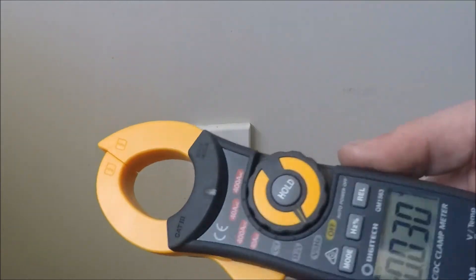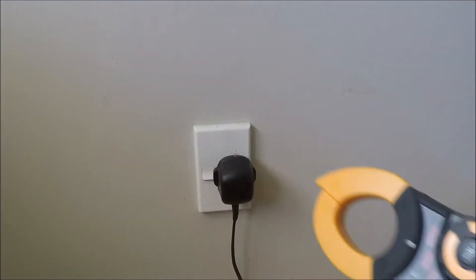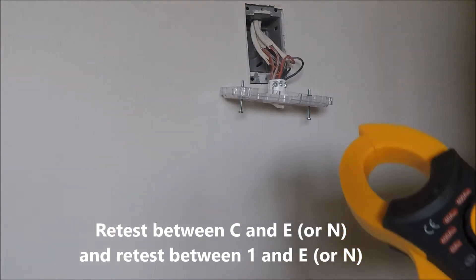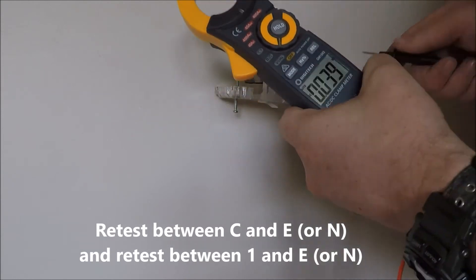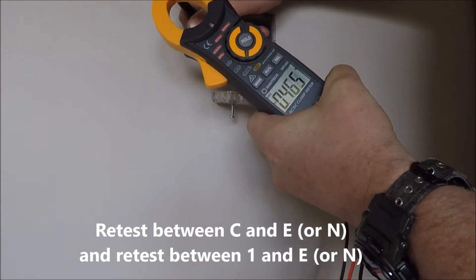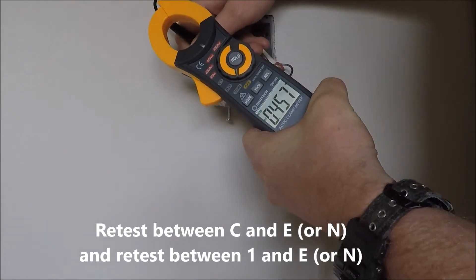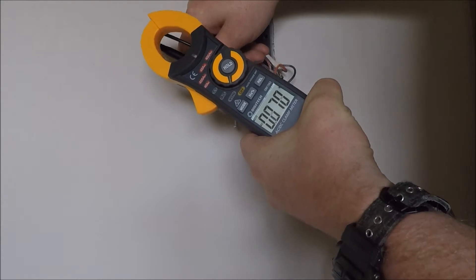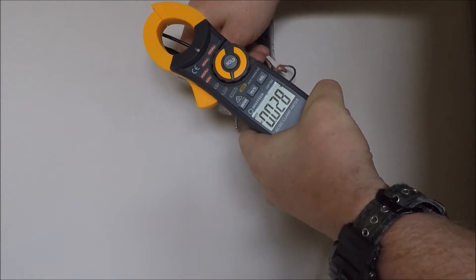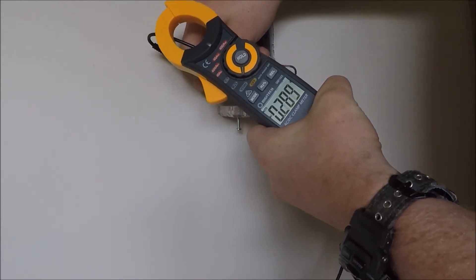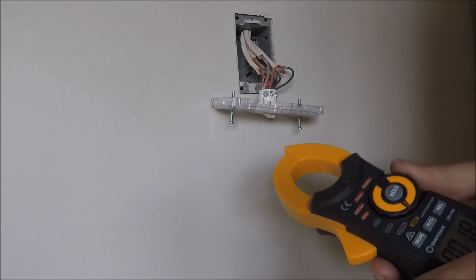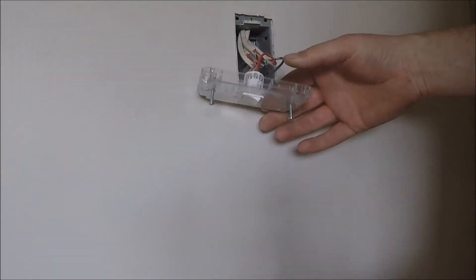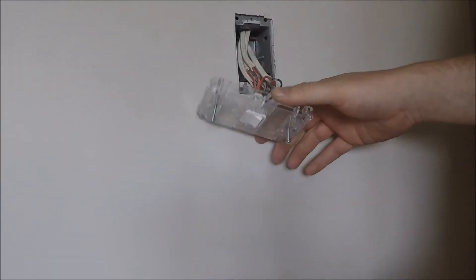So now we've got to re-prove that the circuit is dead. So we're back at the light switch. And what we do is we go from common to neutral, nothing. One to neutral, nothing. It's dead. It's safe to work on, I should say.